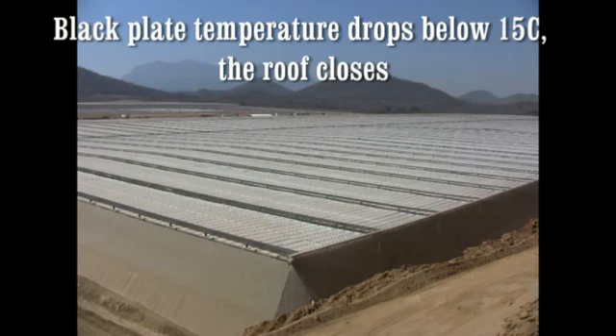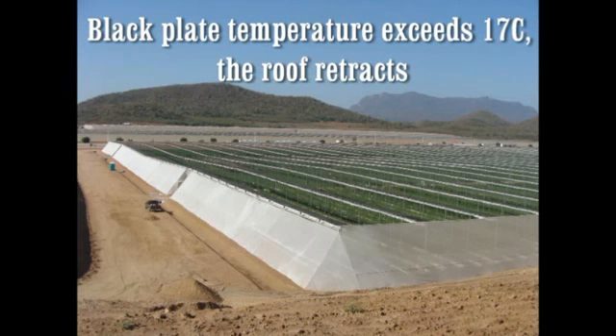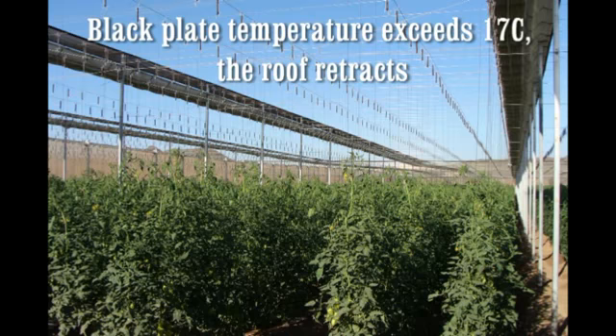When the black plate temperature drops below 15°C, the roof closes to trap heat. When the black plate temperature exceeds 17°C, the roof retracts, exposing plants to direct sunlight. And when the black plate temperature exceeds 28°C, the roof closes 85% to 90% to prevent exposure to excessive heat.